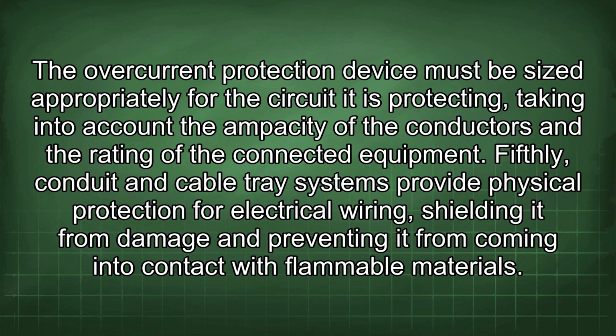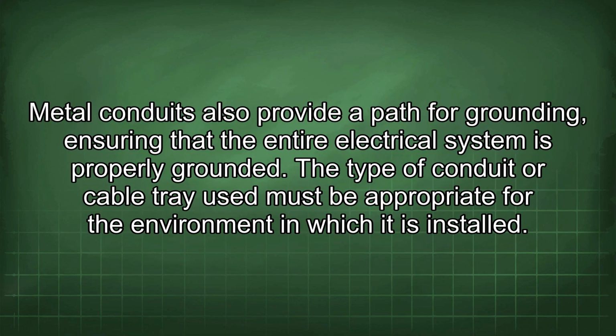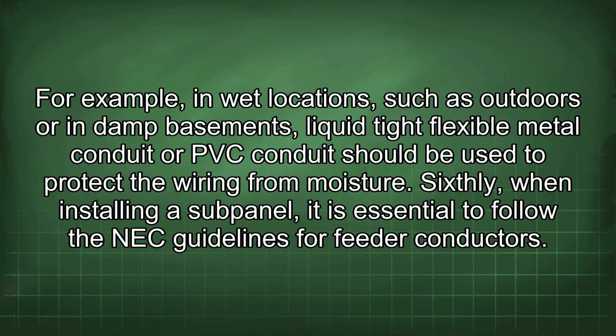Fifthly, conduit and cable tray systems provide physical protection for electrical wiring, shielding it from damage and preventing it from coming into contact with flammable materials. Metal conduits also provide a path for grounding, ensuring that the entire electrical system is properly grounded. The type of conduit or cable tray used must be appropriate for the environment in which it is installed. For example, in wet locations, such as outdoors or in damp basements, liquid-tight flexible metal conduit or PVC conduit should be used to protect the wiring from moisture.